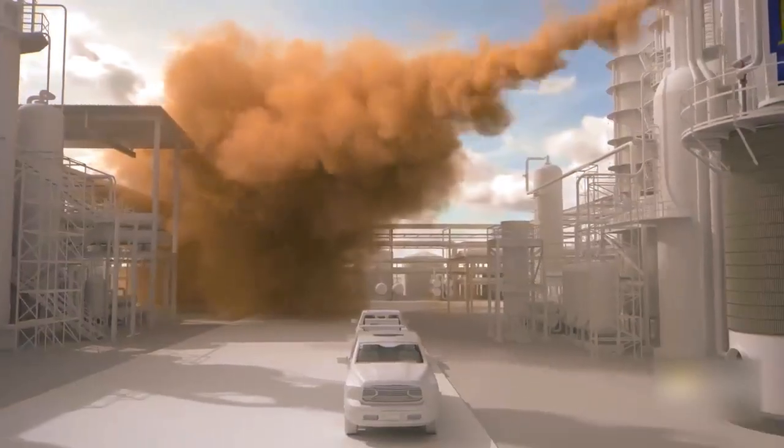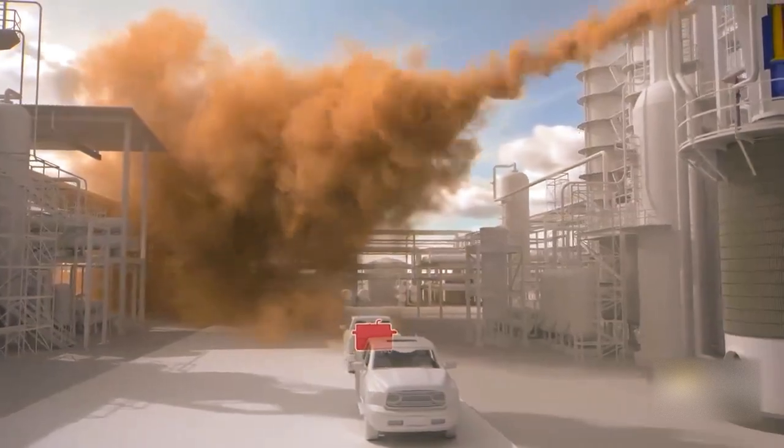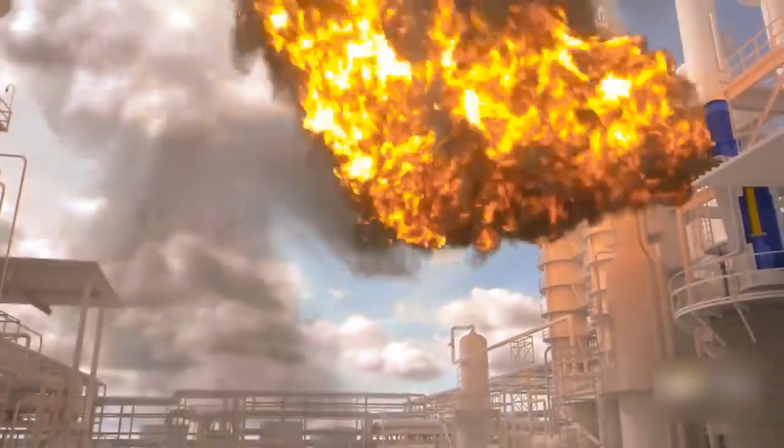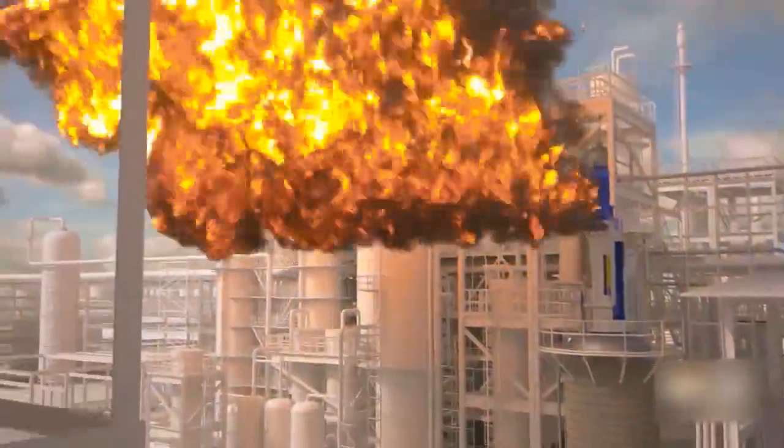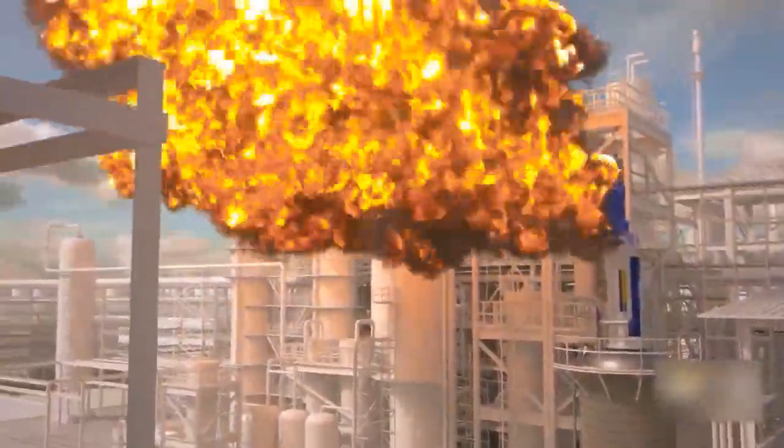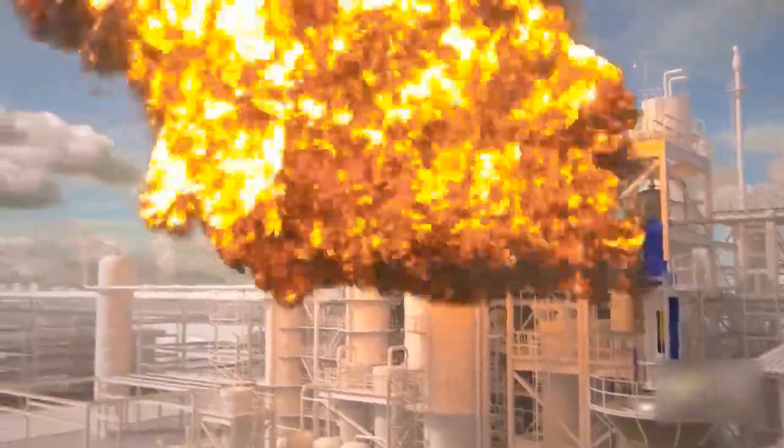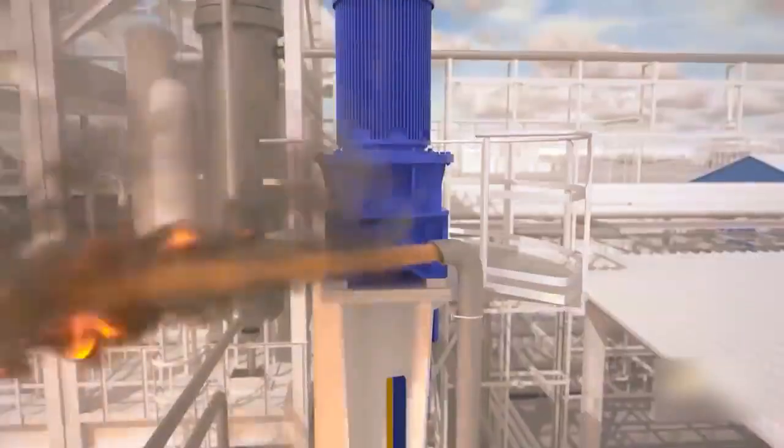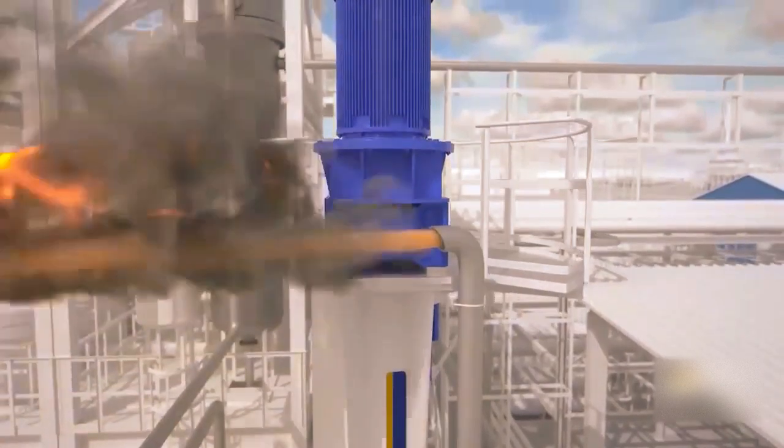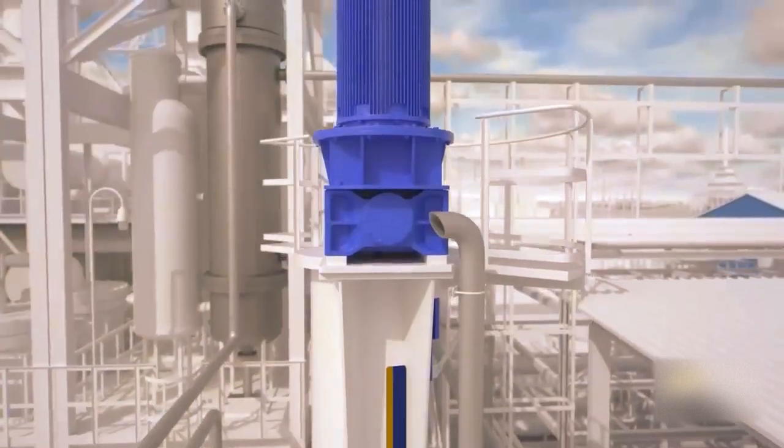Soon after, a nearby welding machine likely ignited the vapor and a large fire erupted. Twenty-three people were injured, many as they urgently tried to evacuate. The ethylene-fueled fire stopped after approximately three minutes, when the emergency relief valve closed as pressure in the reactor normalized.